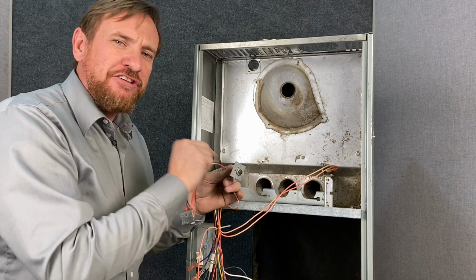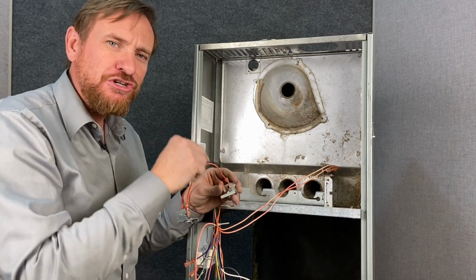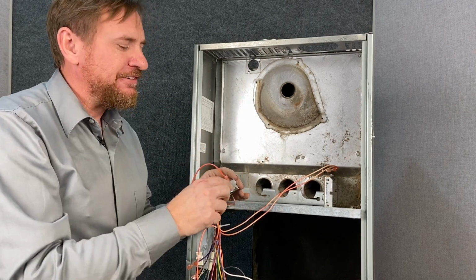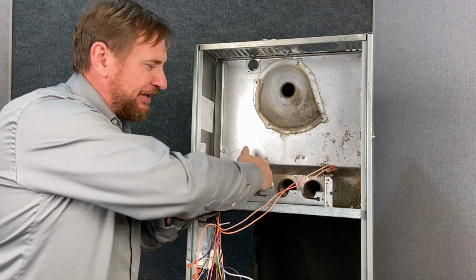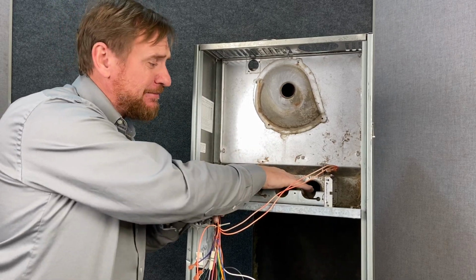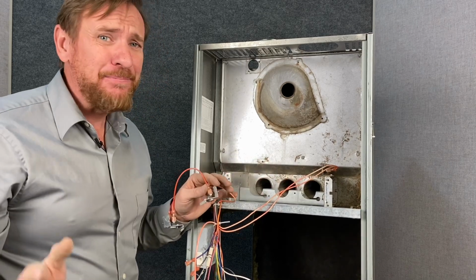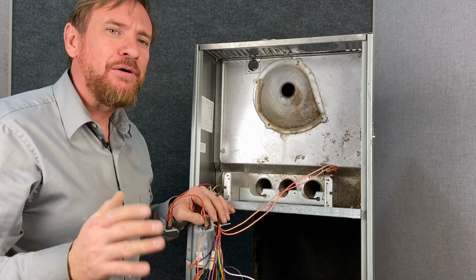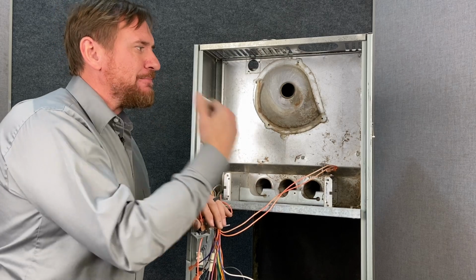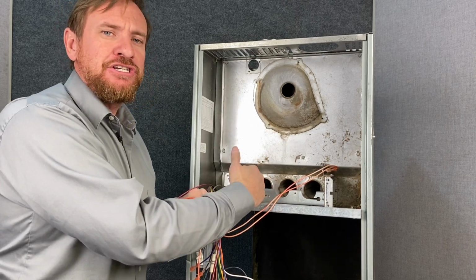Now, you don't just press that button. Here's what I want to stress. You don't just press that button. You also need to find out what caused it. What caused the flame to roll out of this heat exchanger? If that flame is coming out of this heat exchanger, that's a big problem. We want to know why. What caused that to happen? There's many things that cause that. Usually a combustion analysis checks that.